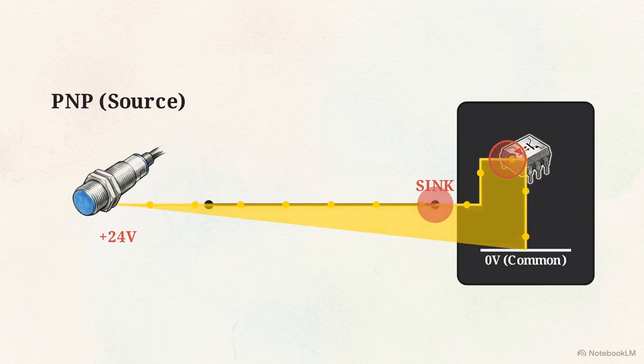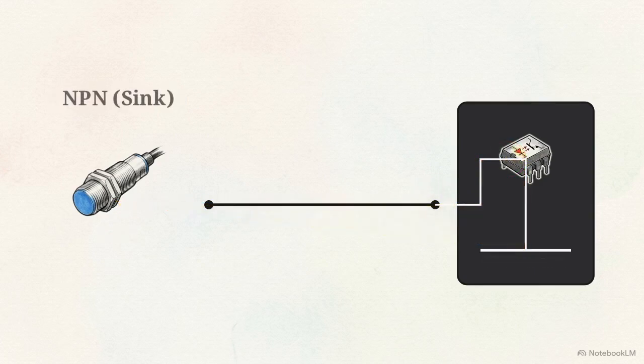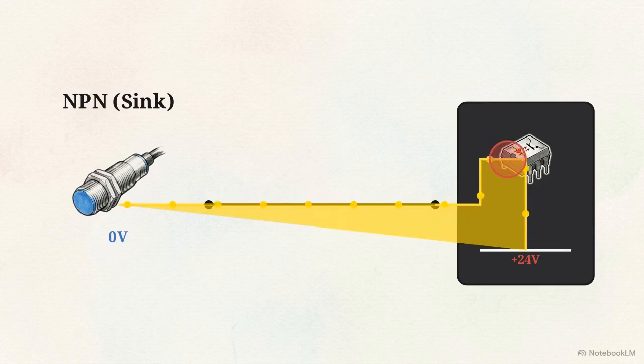An NPN, or sink input configuration, does the exact opposite. The internal common of the PLC is tied to 24 volts. The sensor now acts as a switch to ground, drawing current away from the controller. In this NPN setup, the PLC terminal is actually the source, pushing current out into the field device.